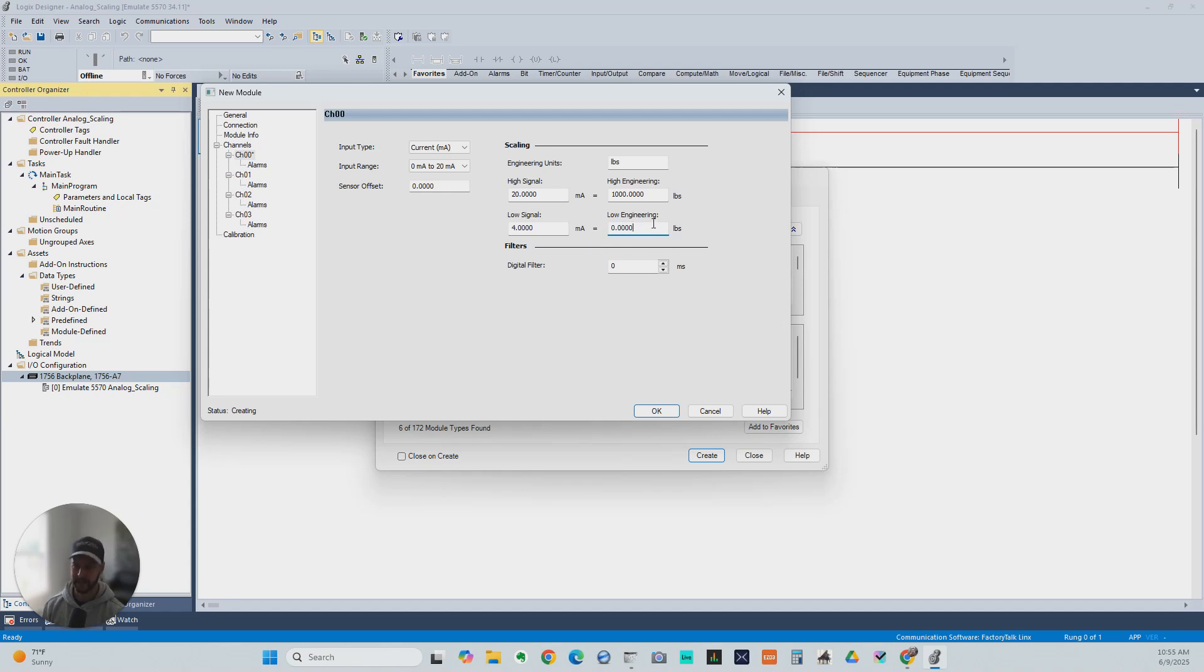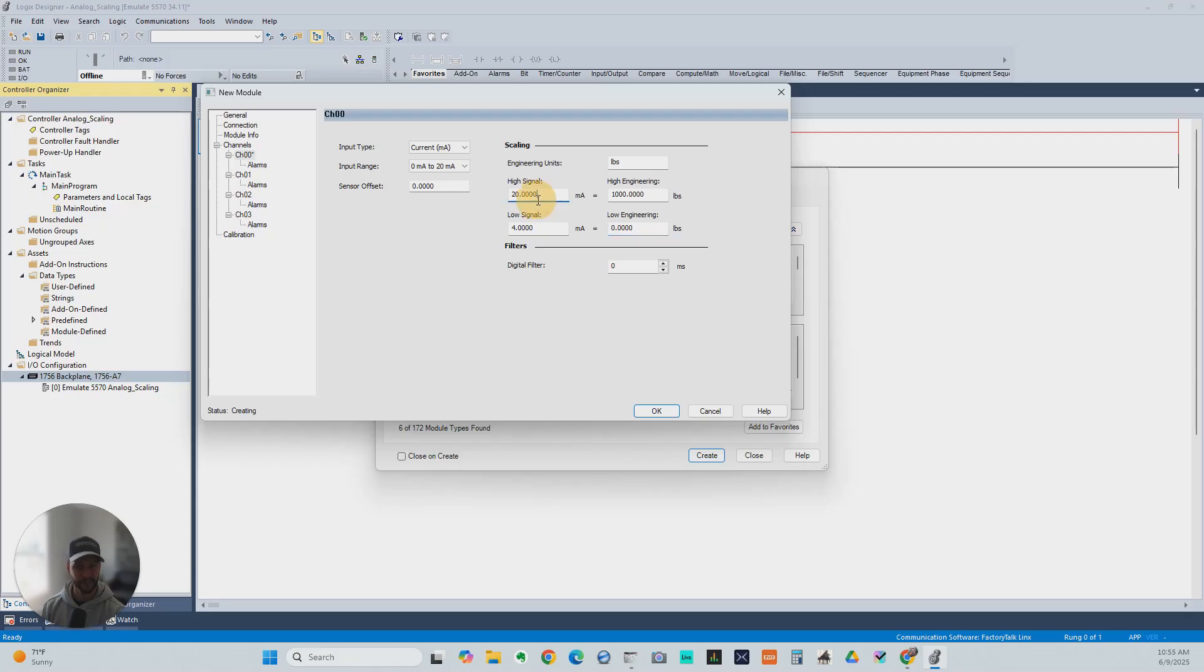We just know, when the low signal is showing 4 milliamps, we want that to indicate that we're at 0 pounds. And when it's showing 20 milliamps, we want it to show that it's 1,000 pounds.